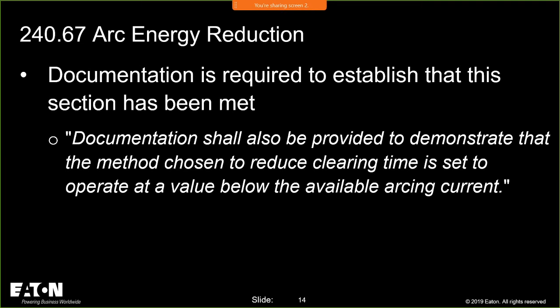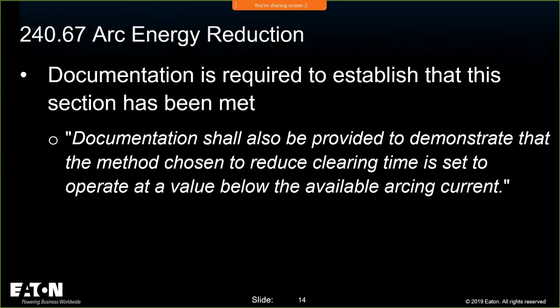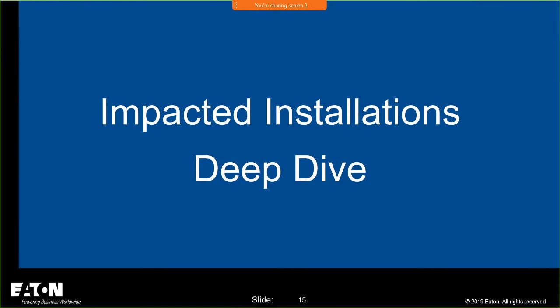I think that's important. Here's what I think is going to happen. Because we're going to be consciously thinking about arcing current at these devices, we're going to be making conscious decisions to ensure the technologies for reducing incident energy are employed and functioning. So that may change how we design a system. You may break those overcurrent devices down into smaller overcurrent devices with the same bolted fault current, and that will help those devices act faster. But you're going to be making conscious decisions everywhere you have a fuse or circuit breaker 1200 amps and above. So we're going to do a deep dive.